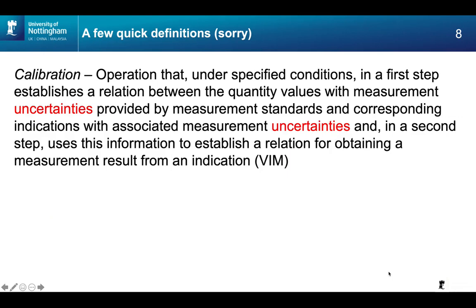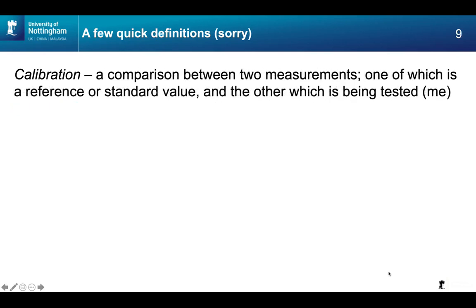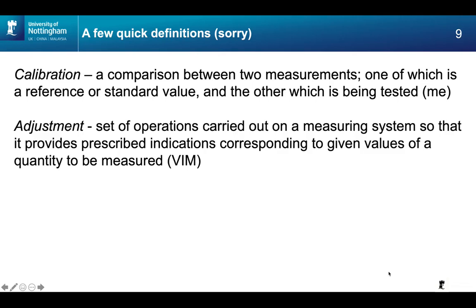Second to last definition. What's calibration? Well, there is a definition in the vocabulary of metrology. I'm not going to read it out. You can see it's quite a long definition. I'm personally not sure I completely understand it. So here's my definition of calibration. It's a comparison between two measurements, one of which is a reference and the other which is being tested. So calibration is that comparison process, and it's absolutely essential that when we do that calibration process, we have uncertainty in the measurement. The reason we need uncertainty is because you cannot compare two measurements unless you understand their uncertainty. You just don't know whether those numbers are equivalent or not without a statement of uncertainty.